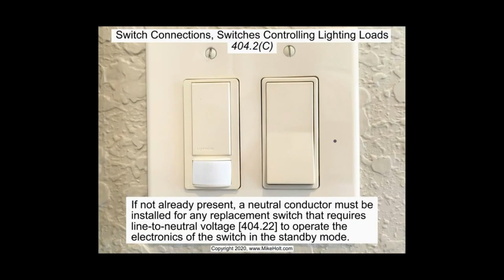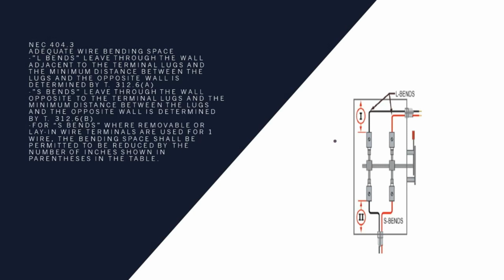You're also not allowed to have a dimmer there. We don't want to put your vacuum on a dimmer. If not already present, a neutral conductor must be installed for any replacement switch that requires a neutral to line to neutral voltage and operate by the electronics of the switch in standby mode. So if you put a motion detector in there and it requires a neutral, technically you're not supposed to be using the ground, because that would be a violation of 250.6. Objectionable current. We do not want objectionable current on our grounding conductor.